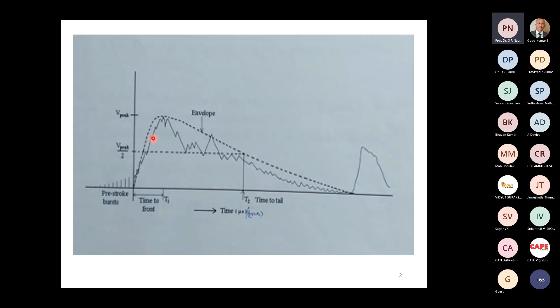Sharper the time to front, more severe the stresses on transformer windings. This is a very important point to first note. If you apply a very sharp time to front to a transformer winding, there will be concentration of the voltage stress at some parts of the winding. Therefore, that can fail. To avoid this, in the laboratory, we use a much sharper time to front than in real life. That's why even though the real life time to front is about 5 to 10 microseconds, in the laboratory we choose 1.2 microsecond as the standard, plus minus 30% as the tolerance. Earlier, 50% was the tolerance, but it has been reduced to 30% because generation has become much simpler today. Therefore, the time to front should be smaller than this to make it more severe on the transformers. Therefore, it's 1.2 plus minus 30% time to front.